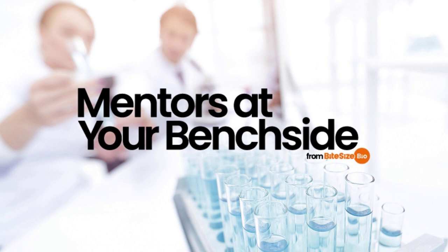Try not to use really concentrated acids to pH your solutions. They tend to change the pH of most solutions suddenly. So suddenly, you can overshoot easily, and we all love starting again when we're already sweating in latex gloves and just want to go home. And always add diluted acid to your test solution and not the other way around. Dilution of acids is strongly exothermic, as already mentioned. Diluting the acid into your water-based solution, which is present in large excess, means there's plenty of water to soak up the heat that is liberated. Conversely, adding drops of water to a strong acid may generate enough heat to boil the water and spray it over you. Physics also exists, so leave just enough spare volume for adding acid or base to your solution unless you want to start all over again.